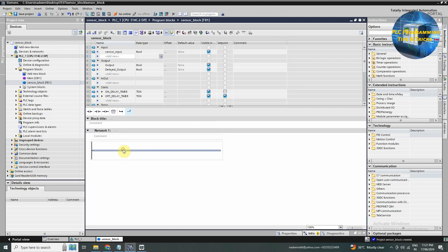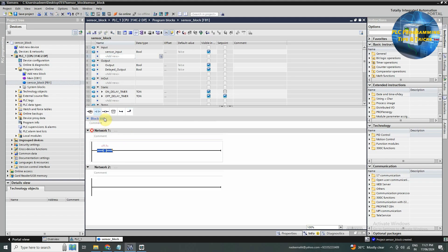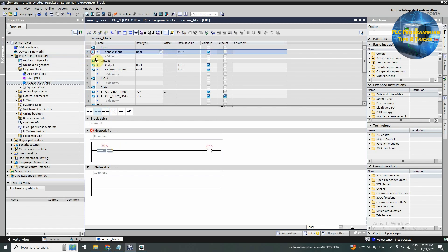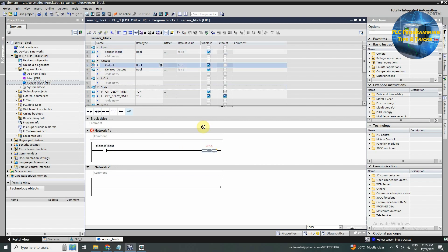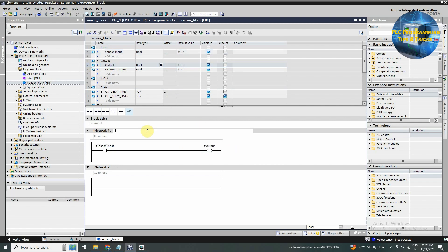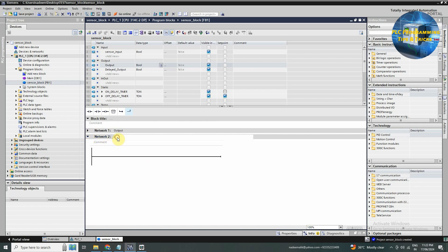Next we will make a ladder logic for the sensor block. In network number one, we will drag and drop a normal open contact and output coil. We will assign sensor input tag to this normal open contact and output tag to this coil. Now this output tag will be energized as soon as the sensor input turns on.